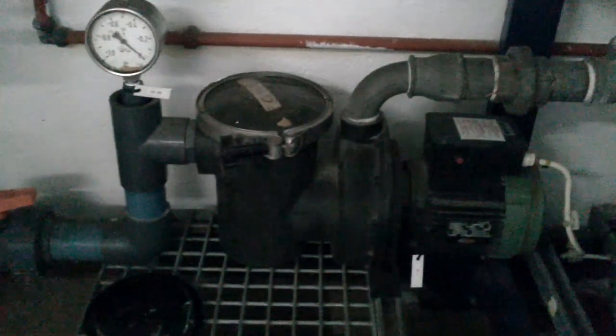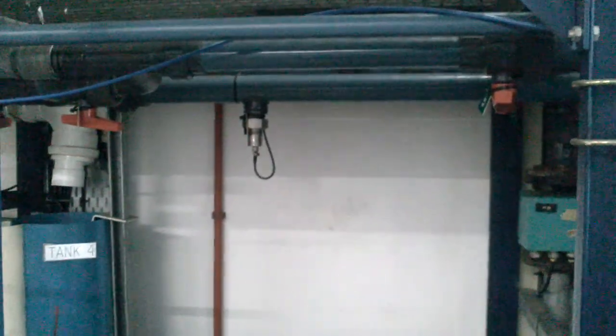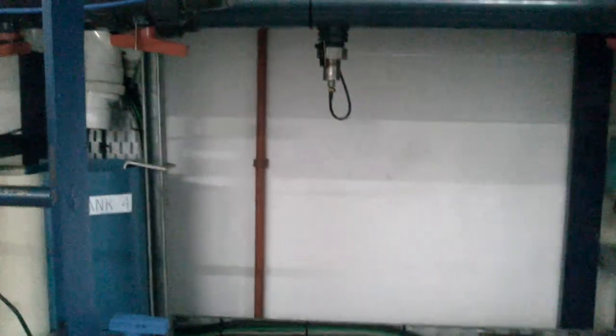What this project does is we take water from here, tank 1, you can see the water there. We get the water using this pump, pump 1, and the pump pumps the water up to tank 7. Then this tank 7 is used to provide a header of the liquid. My desired one is 40%, and then I will control the level of tank 2 to whichever set point I want. In this case, I'm going to test it using set point 50%.